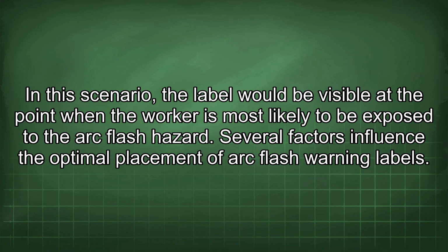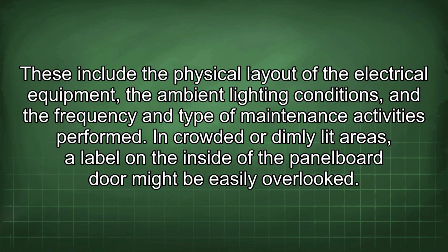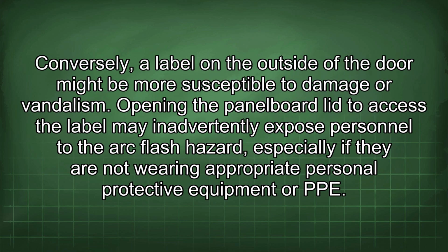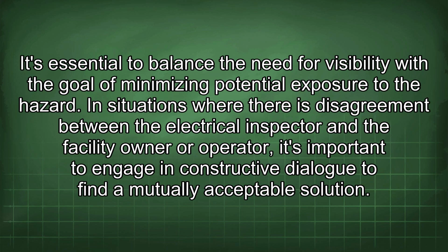Several factors influence the optimal placement of arc flash warning labels. These include the physical layout of the electrical equipment, the ambient lighting conditions, and the frequency and type of maintenance activities performed. In crowded or dimly lit areas, a label on the inside of the panel board door might be easily overlooked. Conversely, a label on the outside of the door might be more susceptible to damage or vandalism. Opening the panel board lid to access the label may inadvertently expose personnel to the arc flash hazard, especially if they are not wearing appropriate personal protective equipment, or PPE. It's essential to balance the need for visibility with the goal of minimizing potential exposure to the hazard.